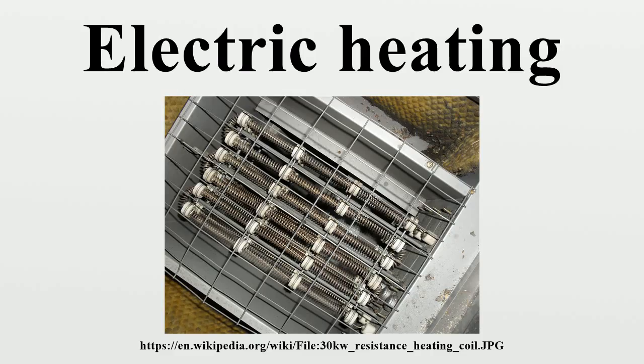Electrical immersion heaters may heat water immediately adjacent to the heating element high enough to promote the formation of scale, commonly calcium carbonate, in hard water areas. This accumulates on the element, and over time, as the element expands and contracts through its heating cycle, the scale cracks off and drops to the bottom of the tank, progressively filling up the tank.